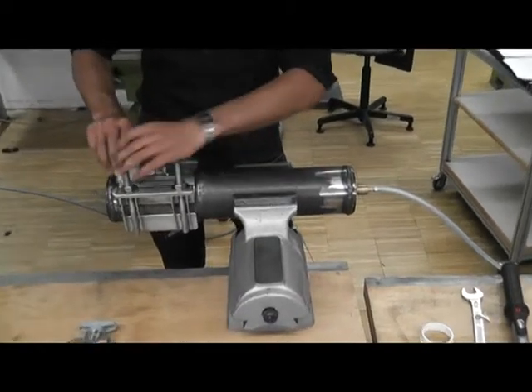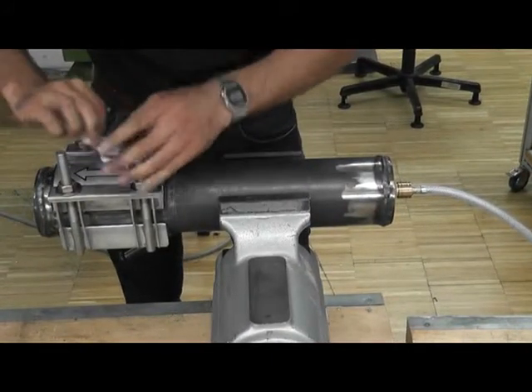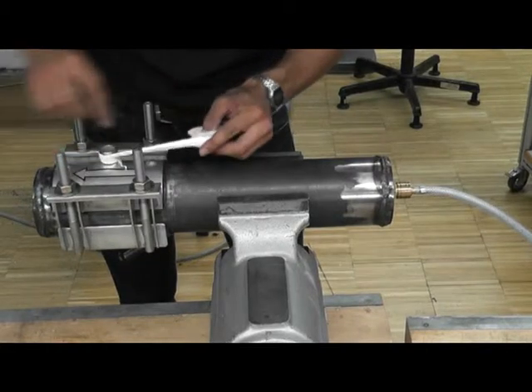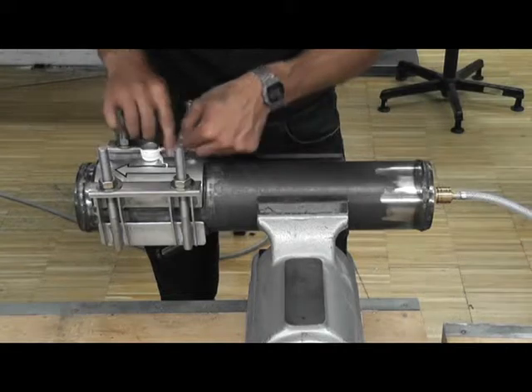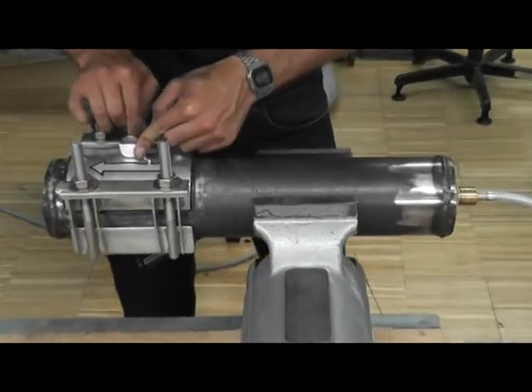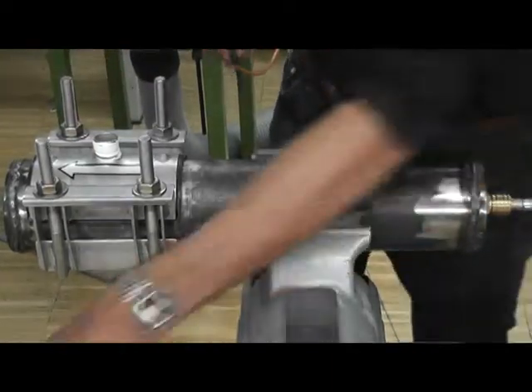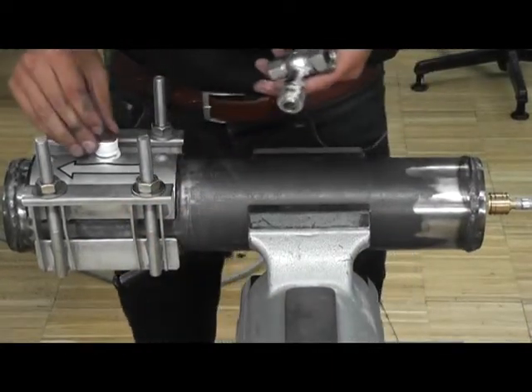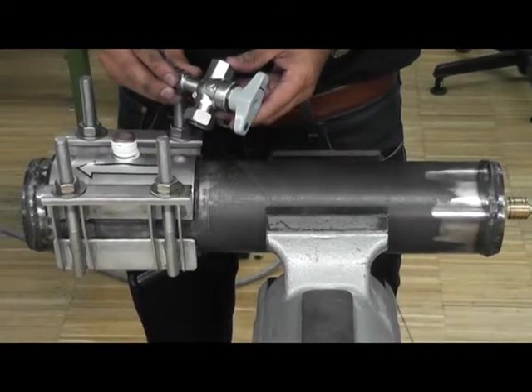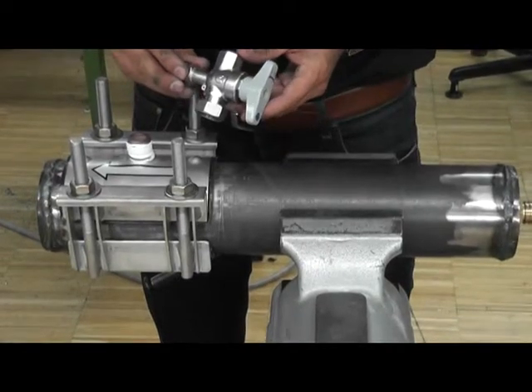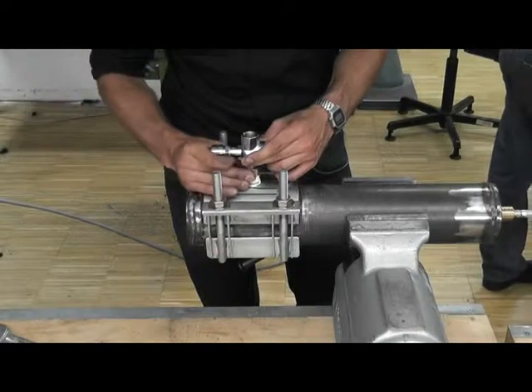The ball valve is one of the most important security parts for the installation of the 6448 under pressure. Before screwing the ball valve onto the tapping clamp, use some teflon tape around the screw. Furthermore, add a gasket between tapping clamp and ball valve. Now screw the ball valve into the thread of the tapping clamp and tighten it.